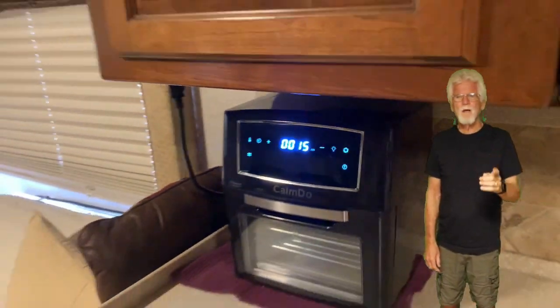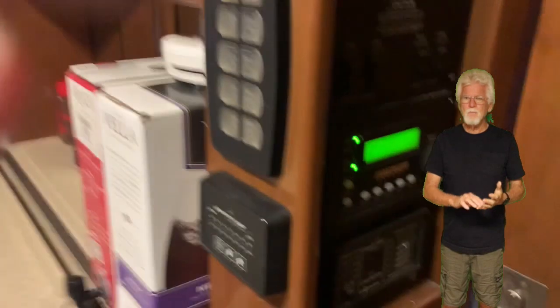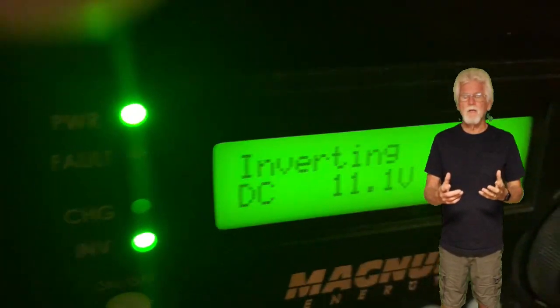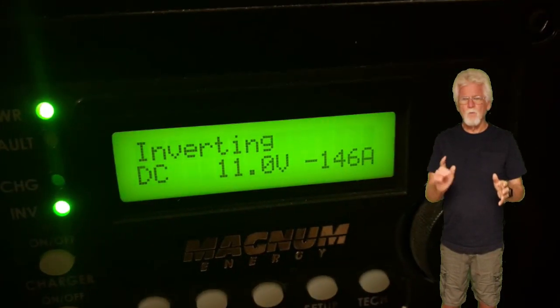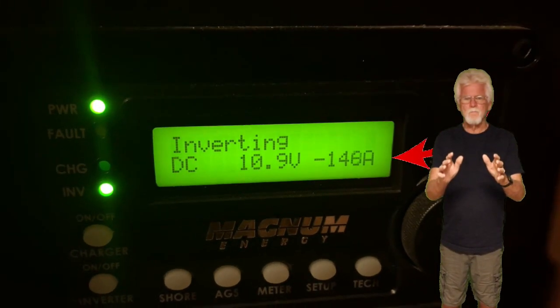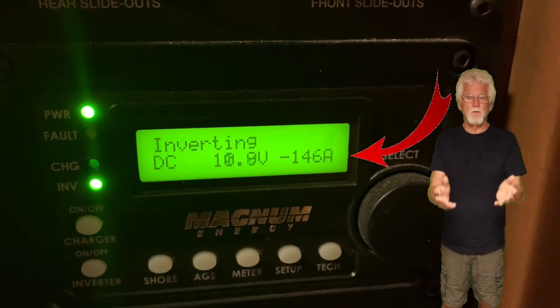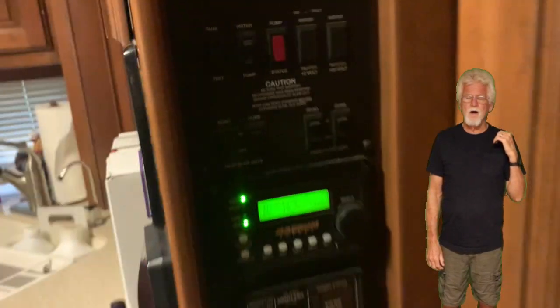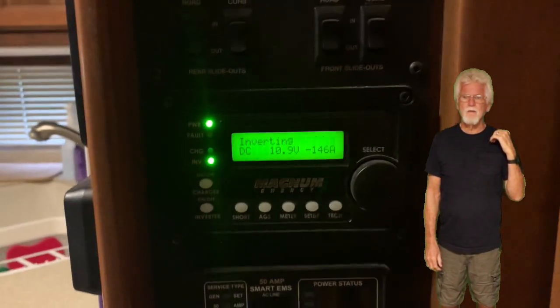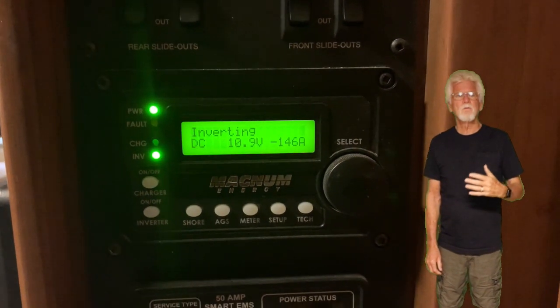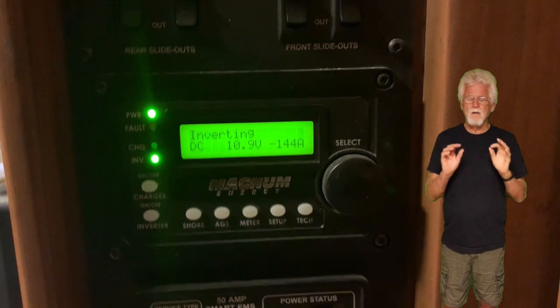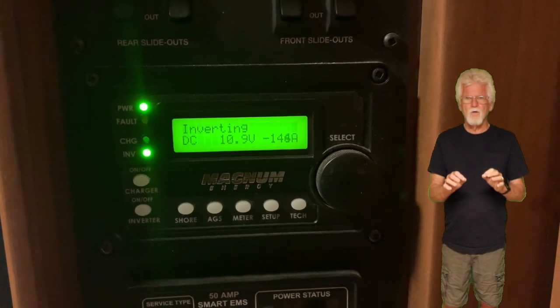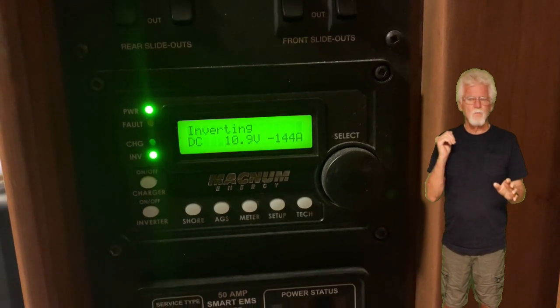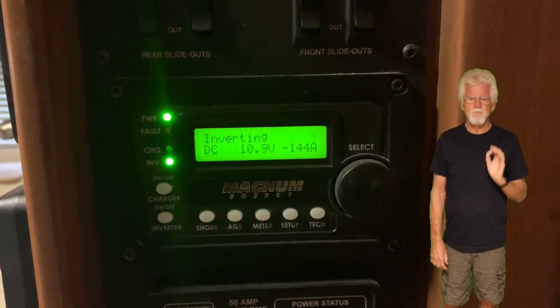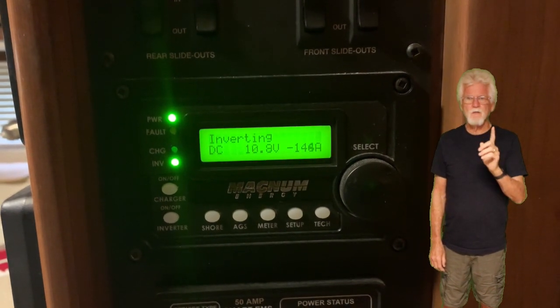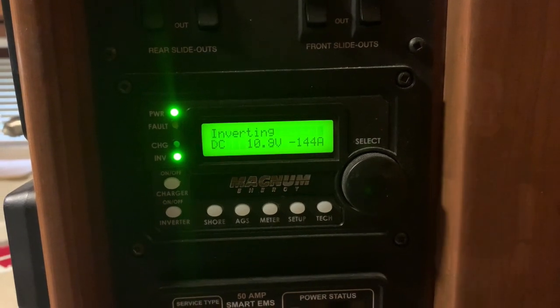We've still got that single battery down in the battery compartment. We charged it up, discharged it, and charged it back up again, and now we're going to see just how many amps that one battery can output. It's rated for 100 amps, so we're testing with our air fryer, which takes well over 100 amps to run. We may get a low voltage fault or an overload fault, but that's not what we're testing — that's just the inverter doing what it does. The objective is to find out how many amps we can get out of a single battery, and it needs to be at least 100.